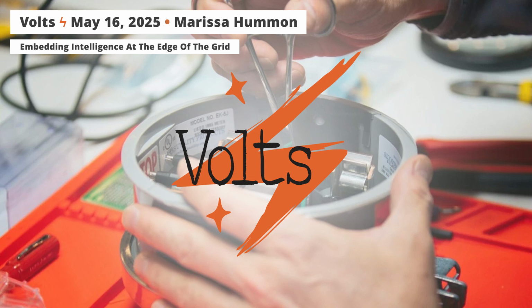We can see specific harmonics in the power quality that tell the utility it's an indicator that other equipment is going to break down sooner. We can see that a transformer's insulation is starting to fail. We can see things like tree branches rubbing against a line, or when a power line starts to become a risk.